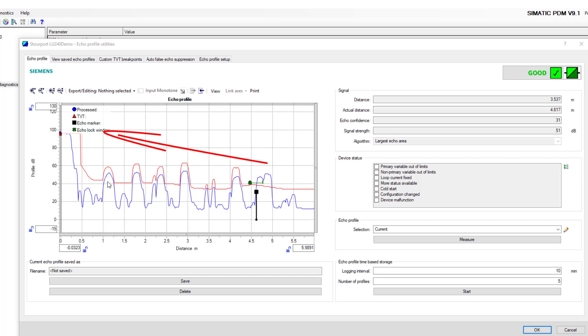There you have it, an overview of echo processing and the results of our non-contact level assault course with the various obstacles we put in the way. Both technologies work. The ultrasonic device required an auto false echo suppression learn, but the radar performed very well.